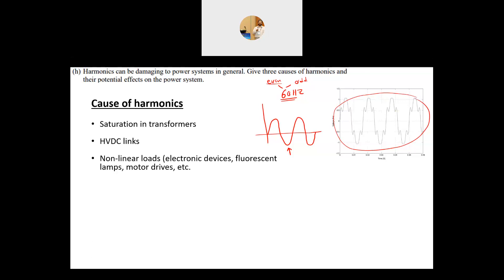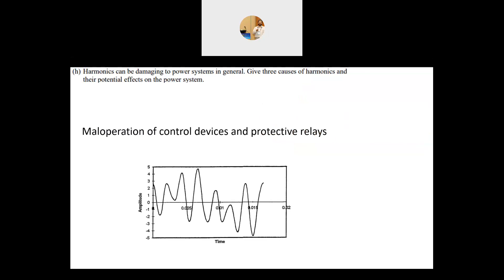But the most important cause of harmonics is non-linear loads. Our loads are not linear anymore—we have electronic devices, fluorescent lamps, motor drives and so on. These types of loads are non-linear and cause harmonics in the power system.